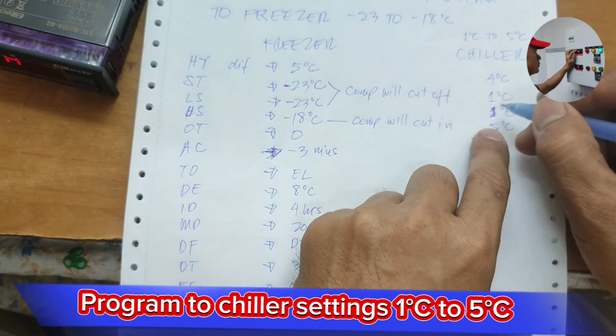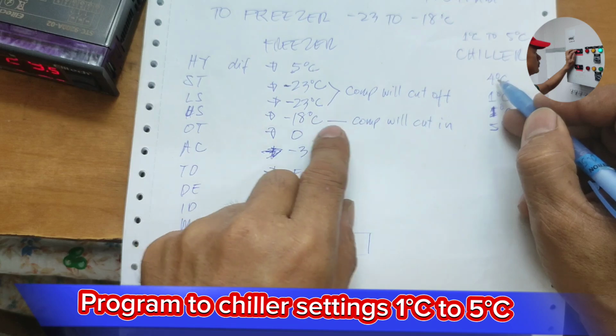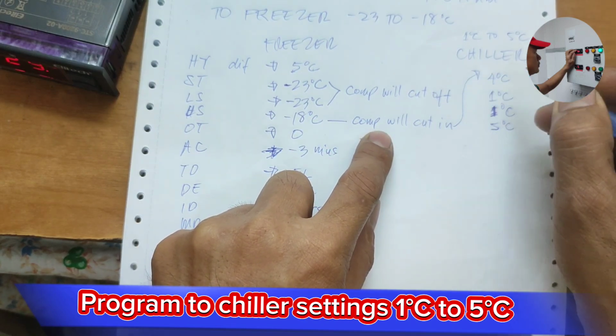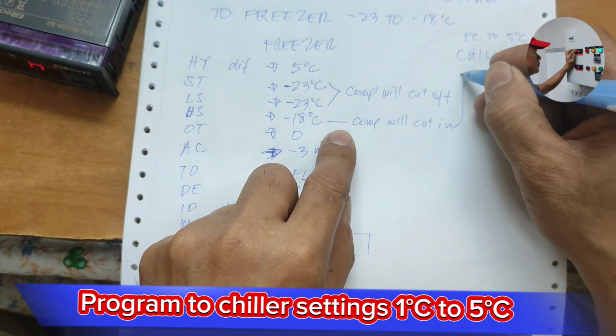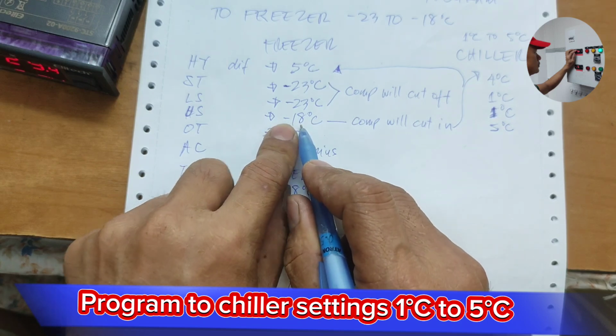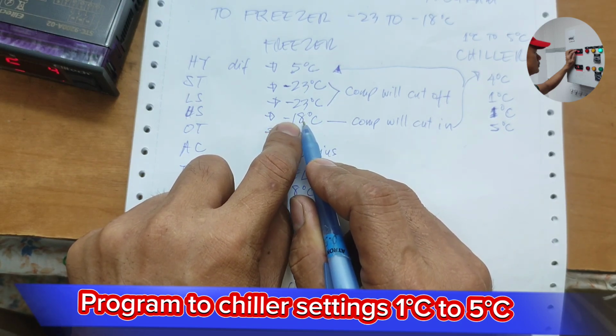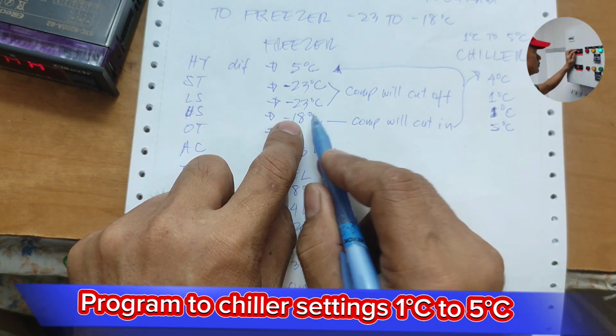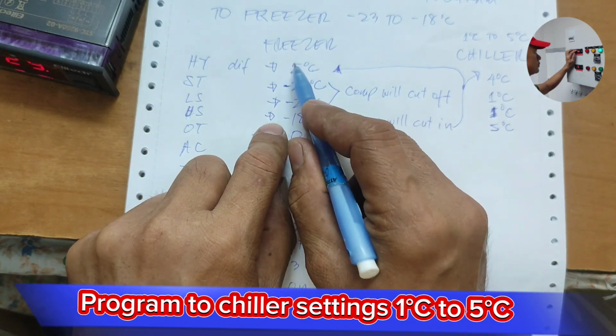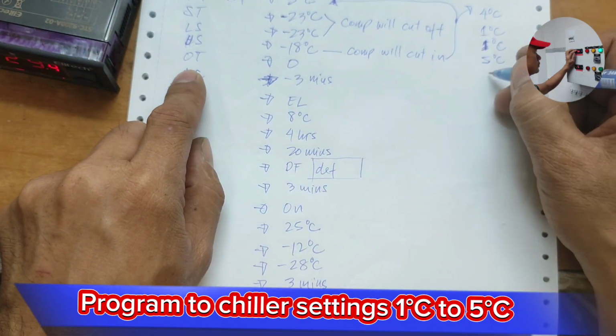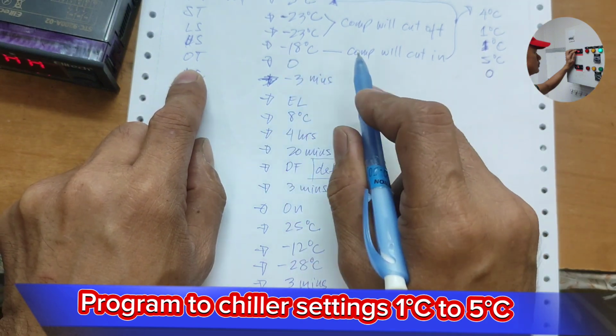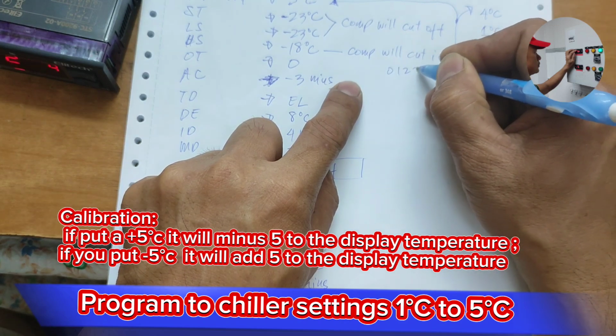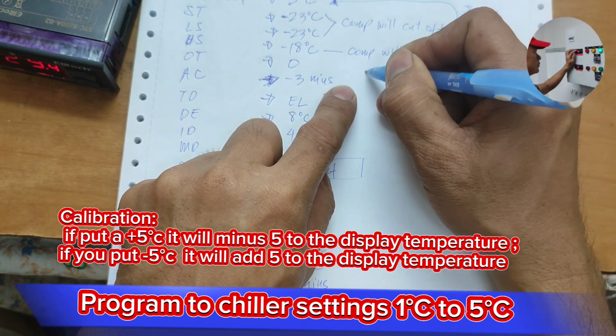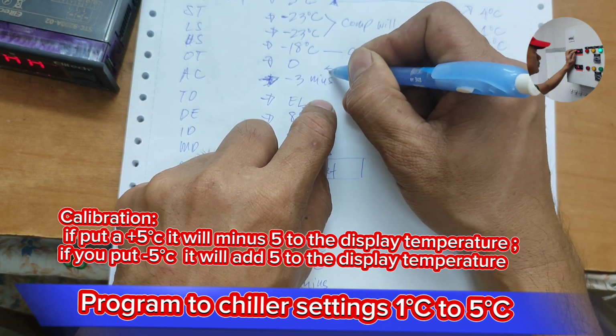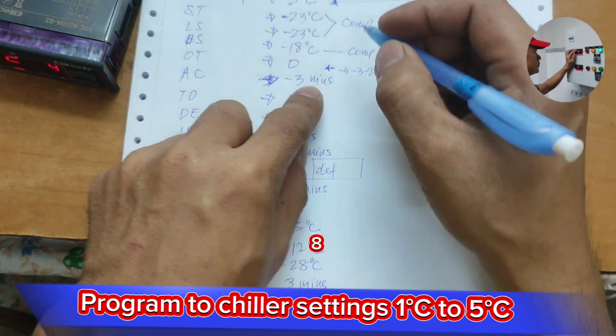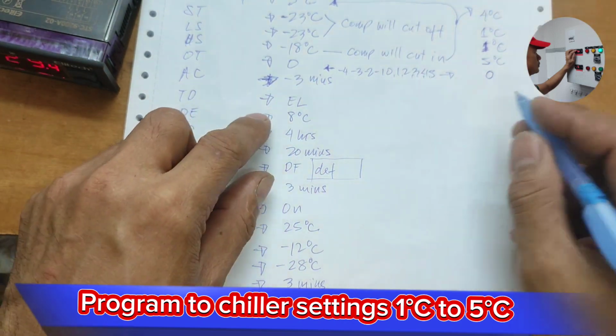And HY, take note guys, the differential is the cut-in of the compressor. Same with this, cut-in of the compressor. The negative rating here is the value when the compressor will start again. It is negative 18, but what triggers the cut-in of the compressor is the value you put in the HY. And then after that, OT, just set it to 0. If you want to calibrate, you can go 0, 1, 2, 3, 4, 5, and so on, and negative 1, negative 2, negative 3, negative 4, and so on. There's a limit, I guess up to 5. I haven't checked yet, I'm not sure, just check the manual.